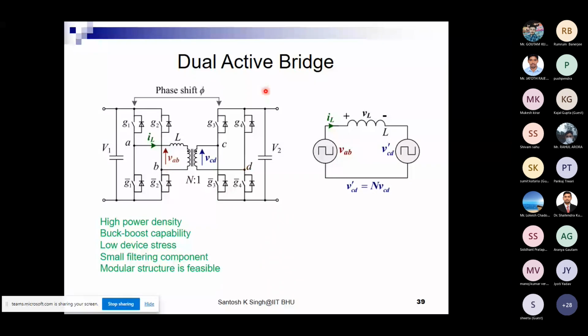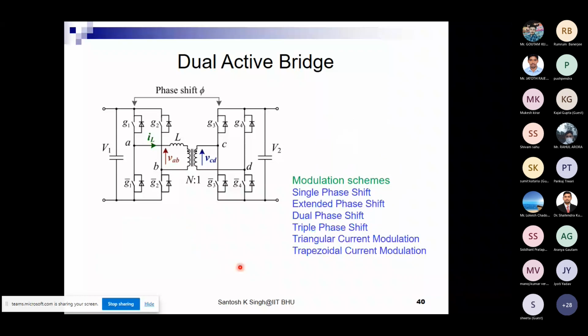We are working at higher switching frequencies, so with higher switching frequencies our filtering requirement comes down, reducing the size of these filters. Then there's the modular structure, a very nice feature of these dual active bridges - if you want to enhance the rating of the converter, or take it for maintenance and repair, you don't need to do a lot together. You can simply take out one stack and put another stack inside, and things can start working. That modular structure is another beauty of it.